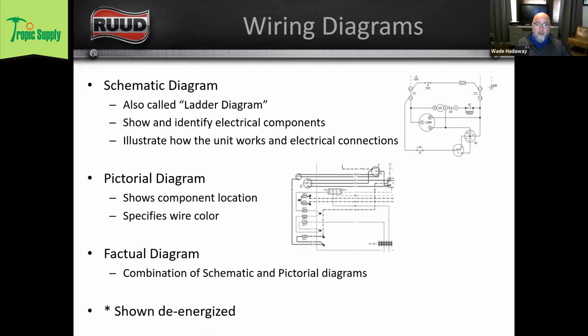Schematic illustrates how the unit works and how the electrical connections are made. These diagrams are all shown in the de-energized position. So anytime you're looking at a schematic or a wiring diagram, just know that it is showing you the position as everything is de-energized. And then the factual is a combination of both of those. Typically that's what you see. If you pull off the panel of one of our units, you're going to see a factual diagram.